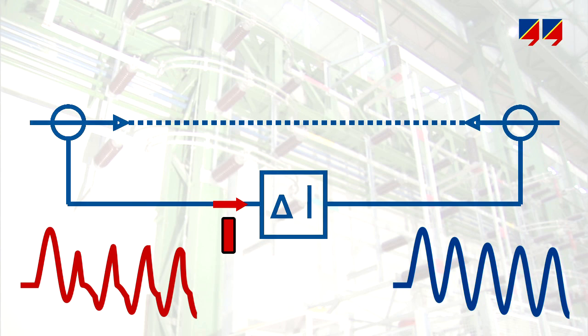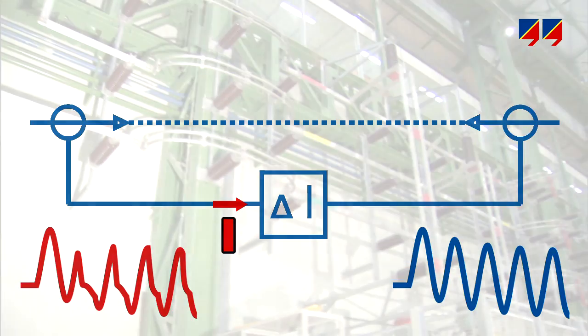Especially for small fault currents, saturation may not be detected by the relay, since its corresponding saturation detection algorithms usually require multiples of nominal current for their activation.